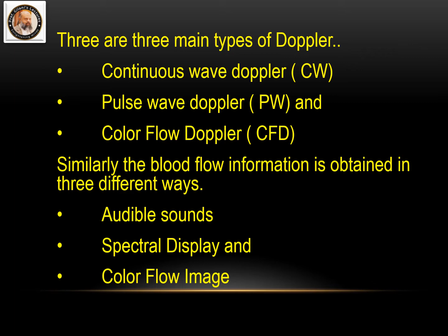There is a difference between continuous wave Doppler and pulse wave Doppler. A pulse wave transducer is a transducer which emits sound waves in the form of pulses. They are sending, then receiving, so they are sending in pulses and receiving in pulses. Whereas a continuous wave Doppler has a transducer case which actually contains two transducers, two emitters. They are continuously sending and receiving. There is no pulse.